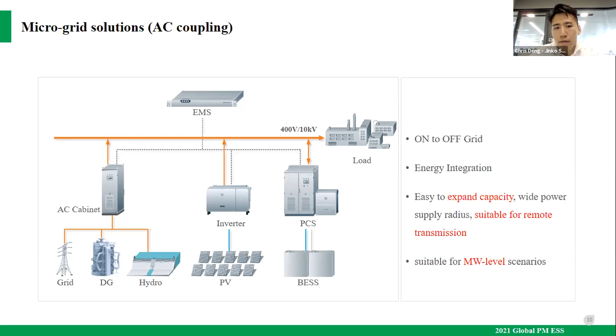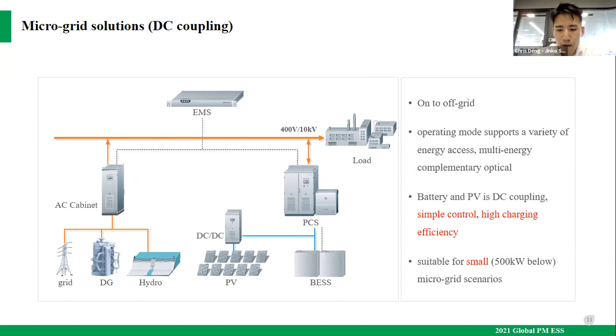When PV generates energy it goes through the DC-DC converter, which handles charging or discharging to the battery. The battery then goes through the PCS side to supply the load. It's more efficient, simpler to control, with high charging efficiency, but it's suitable for smaller systems, I'd say 500 kilowatts or below, more for the microgrid scenario.